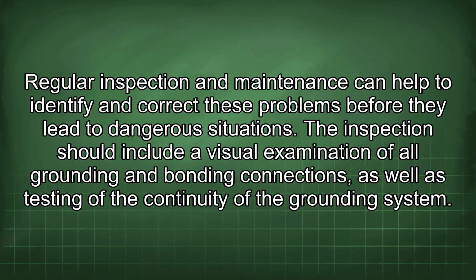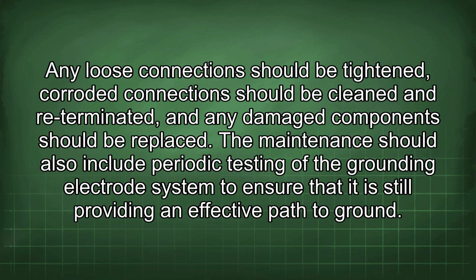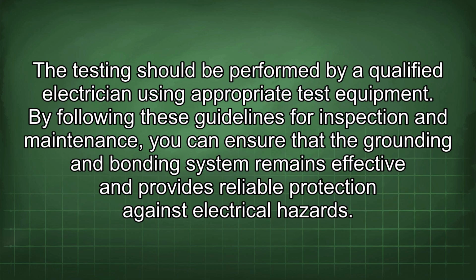The inspection should include a visual examination of all grounding and bonding connections, as well as testing of the continuity of the grounding system. Any loose connections should be tightened, corroded connections should be cleaned and re-terminated, and any damaged components should be replaced. The maintenance should also include periodic testing of the grounding electrode system to ensure that it is still providing an effective path to ground. The testing should be performed by a qualified electrician using appropriate test equipment. By following these guidelines for inspection and maintenance, you can ensure that the grounding and bonding system remains effective and provides reliable protection against electrical hazards.